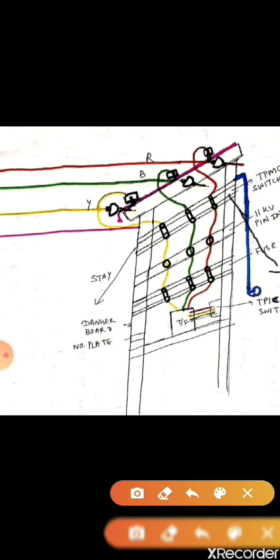Next we will require a substation plate. Here it is the substation plate. The substation plate is required to mount the transformer on it. So the quantity here is 1. Next is MS channel 100 mm into 50 mm into 8 mm into 2.65 meter long. Here this is the MS channel cross arm, and the incoming R, Y, B 3-phase lines are connected to this MS channel through the disc insulator, and the lightning arrestor is also mounted on the MS channel.